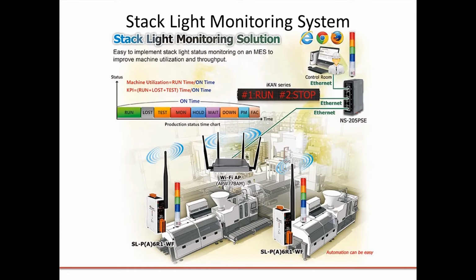The module can be used to detect the status of each color segment of the stack light as being either off, on, or flashing. In addition to detecting the status of each individual color segment, the status of the combination of multiple color segments can also be defined, including the ability to report the duration of the previous and current status. This gives you an automatic way to log and evaluate machine status over time so you can maximize productivity without the need for a lot of special infrastructure.